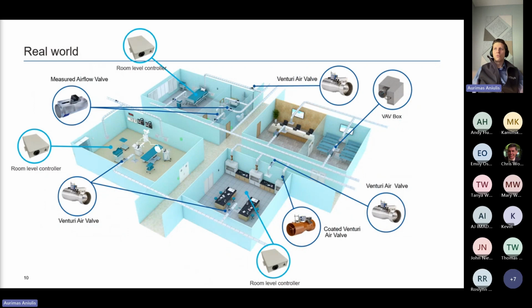This is a real world scenario of what we typically see in a building. You'll have a mix of the spaces that we just discussed, thrown in with some regular waiting areas and receptions. Now, it's important to note that Venturi air valves are the go-to for precision airflow control in these critical spaces like an OR, a lab, or a patient isolation room with some contagious disease. But when it comes to a regular waiting area or reception where we're only doing comfort control for temperature and air changes, where speed of response and accuracy is not so critical, regular VAV box applications is what is typically used.